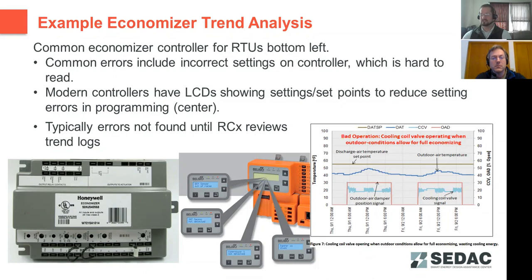But in all these instances, there just has to be some means for your economizer system to report back to the building owner at a centralized location that there's an issue with that economizer that's not working properly. The reason this is such a big deal is if that economizer gets stuck in an open position and you draw in a lot of outside air, that is a lot of excess energy that the building is going to be consuming that they might not even necessarily know ever happens, because the system may be able to, most of the time, keep up with those loads and provide comfort to the occupants. It's just going to use a lot more energy to do so. So that's why this fault detection and diagnostics is an important part of the code.